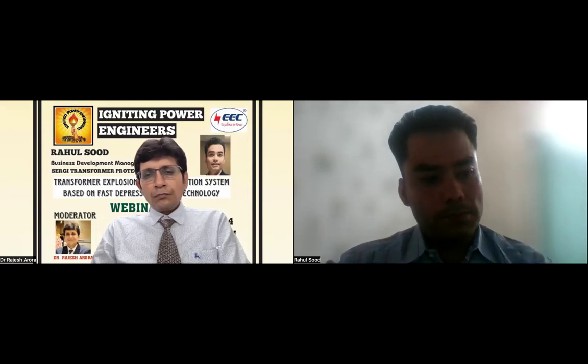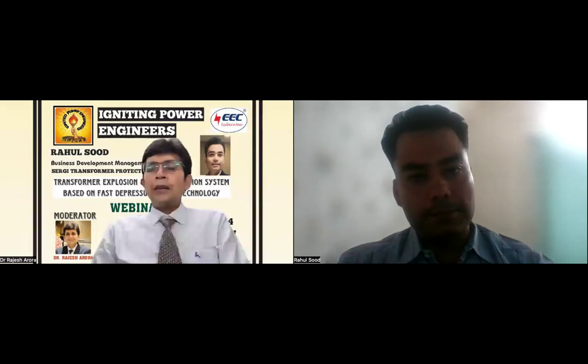So I always suggest to utilities, instead of going for a system that you think will protect your transformer or extinguish a fire, there are so many passive systems that you should follow, like a firewall, things that will not spread the fire, and see that this type of failure does not happen. And one more point, for the interest of those attending this seminar: we should remember that transformer oil basically has the arc quenching property. That is why, as we learned in the textbook, in earlier times it was all oil circuit breakers, where transformer oil was used to quench the arc.